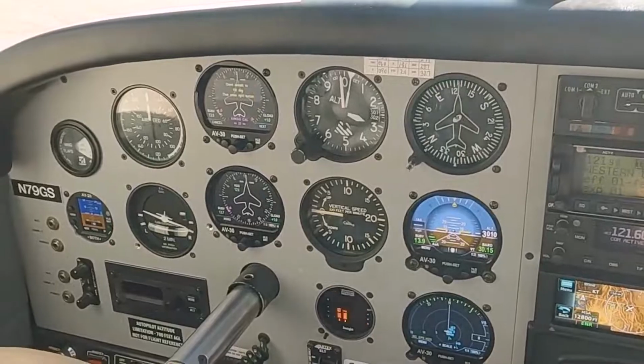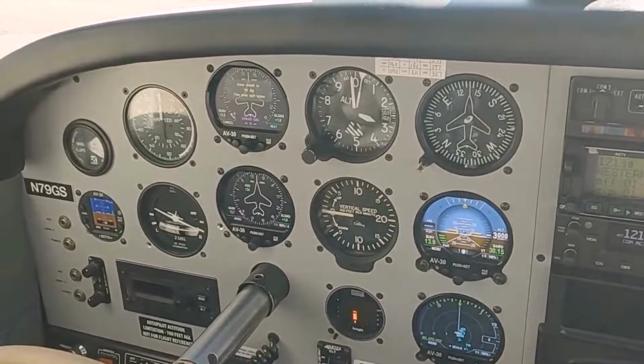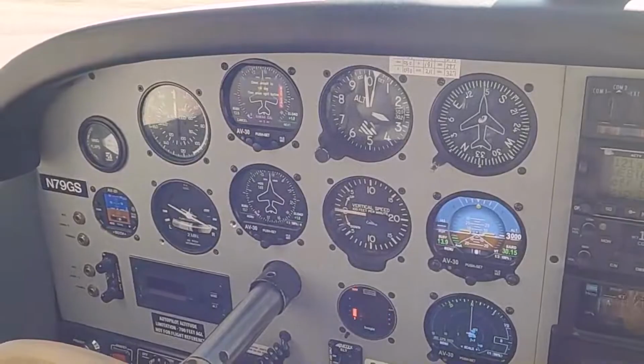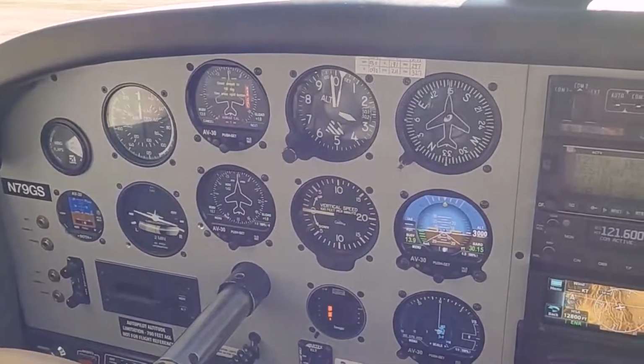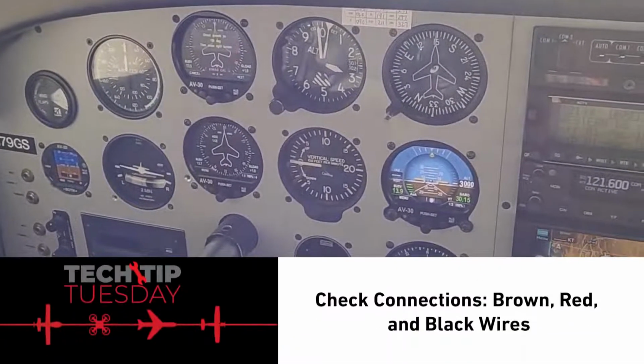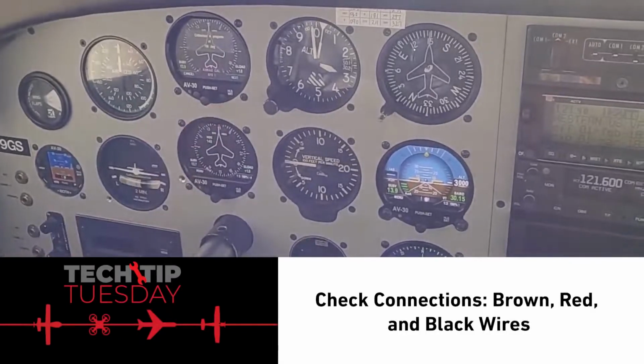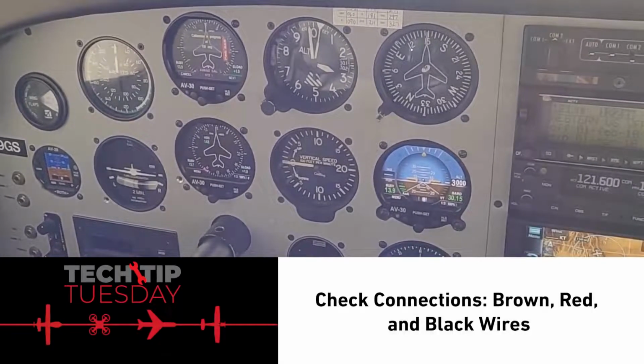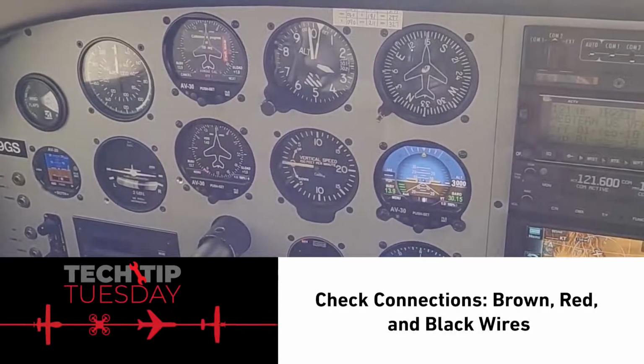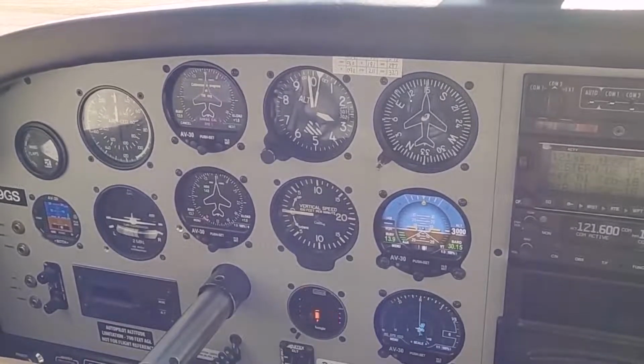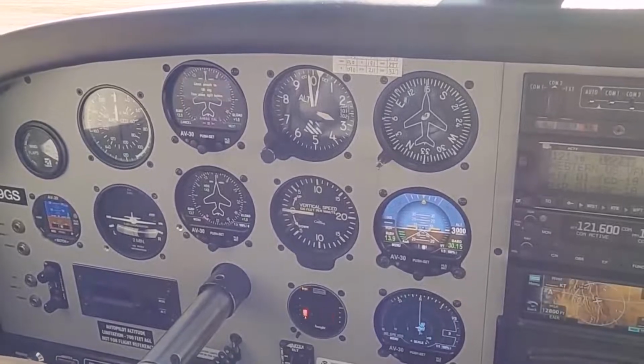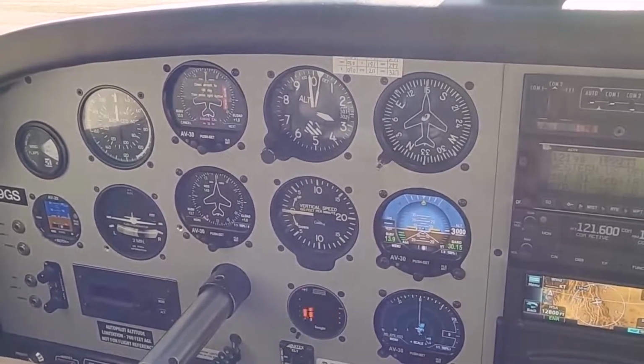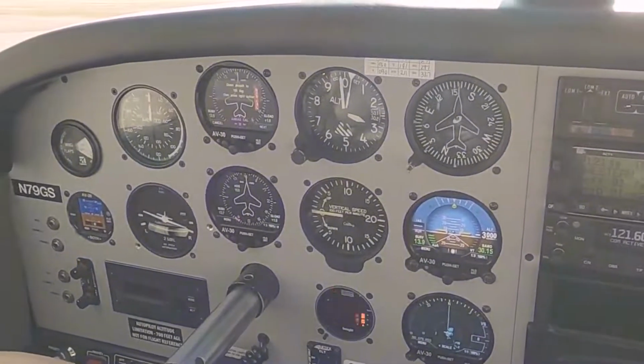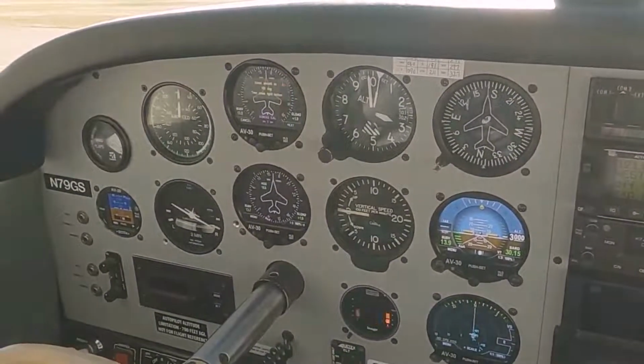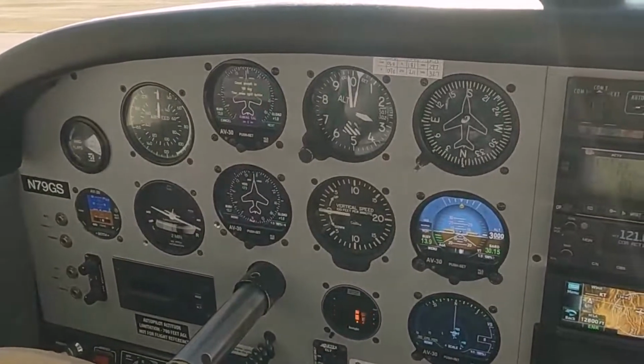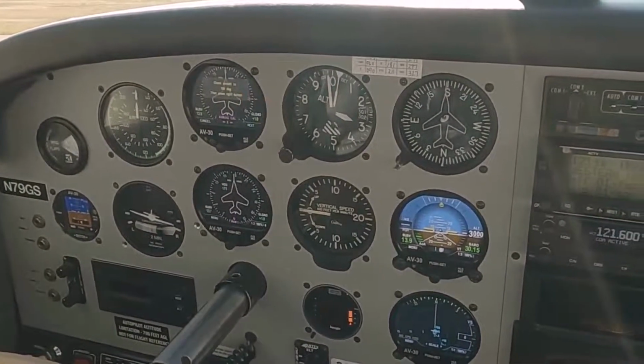So some things to remember while you're doing the AV mag calibration. If for some reason you get a no mag flag, then you need to check and make sure that your connections are correct, that there's nothing prohibiting it from being connected. So you have a brown wire, a red wire, and a black wire, and if any of those are not connected properly, you're not going to get the mag cal. So we know it's working when we get the mag cal. If you have a no mag flag, you will not be able to complete the mag calibration.